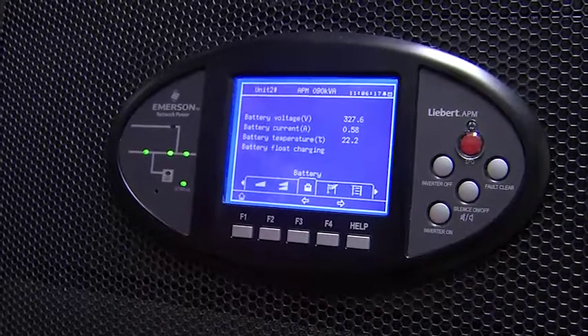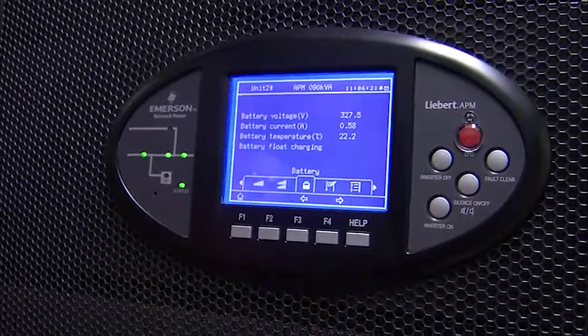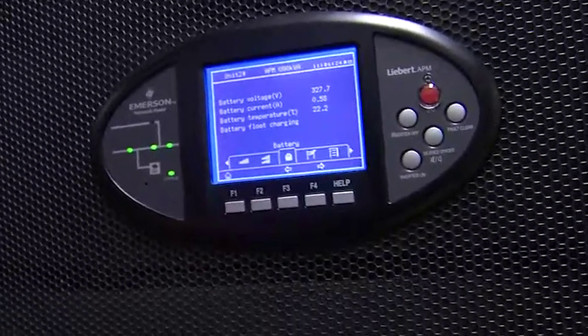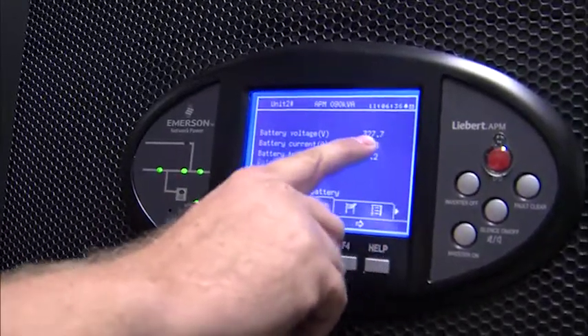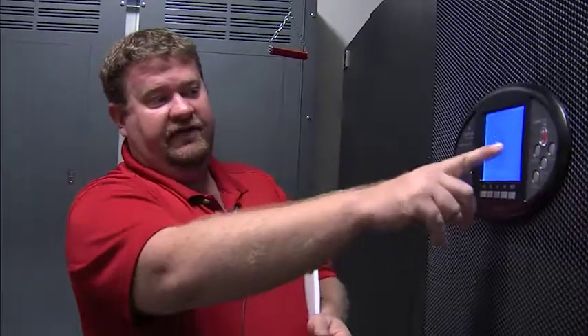And then we get into our battery. On this system, there is monitoring. Are you monitoring with SNMP? Not yet? Okay. On this system, we monitor our battery temperature and our float voltage. On the monitoring system, when you have it remotely, it will tell you how much runtime you have. On this screen, it will not tell you how much runtime there is until it goes to battery. But you can go onto that SNMP when we give it an IP address, and it will tell you how much runtime. And I can calculate this based upon our load and our float voltage. If we need to, I can show you that calculation after we're done.